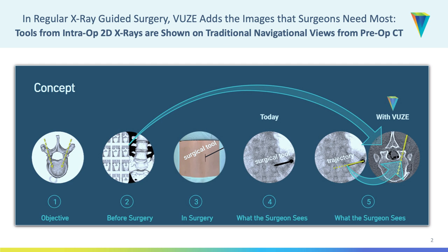We detect the tools in the x-ray images, and the other part of the algorithmic work is to register that x-ray image with a 3D of the same skeletal portion as seen in the pre-op CT. By doing those two things, we virtually implant the tool in the 3D space of the vertebra, and then we can slice the image any way we want — sagittally, axially — and all of it is done online in real-time.